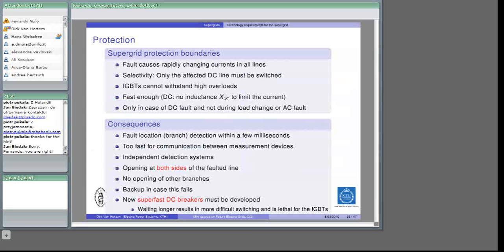So what are the consequences? The fault location, the branch, must be detected within a few milliseconds. It's too fast to have communication between the measurement devices, and you need to have an independent detection system in every protection device. The opening should be done at both sides of the faulted line, and there is no opening of any other branches, of course. Only the ones that are affected should open up. And if this is not working, of course you need to have a backup somewhere. For this you need super fast DC breakers, which don't exist at this moment. And these super fast DC breakers are needed because if you wait longer, you'll burn up your IGBTs.